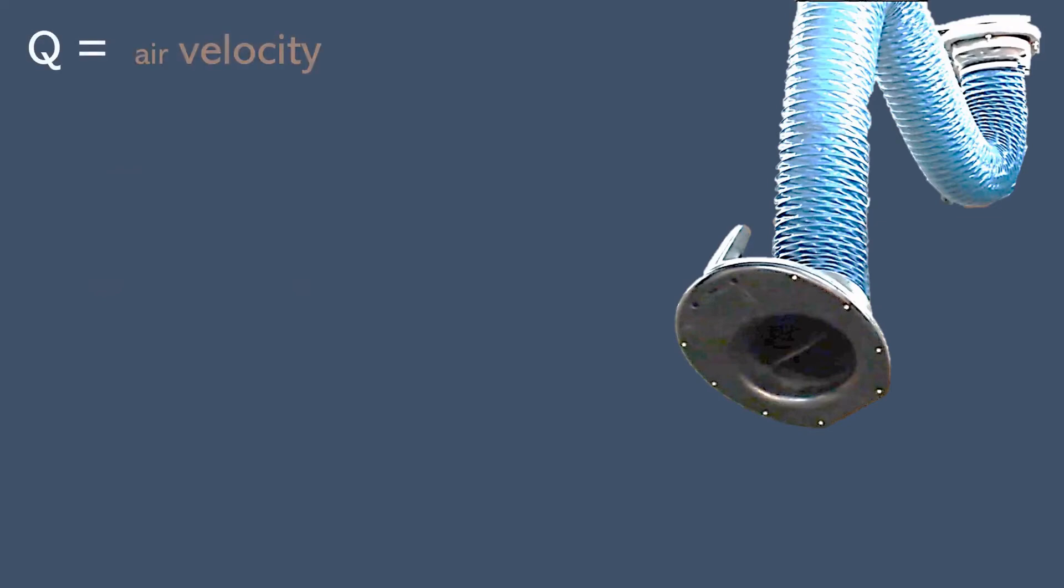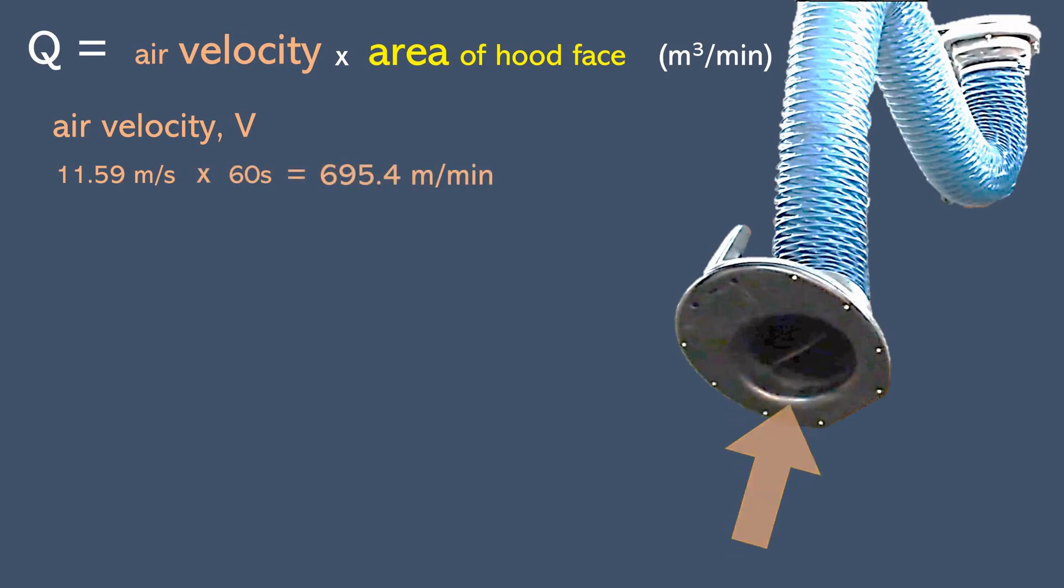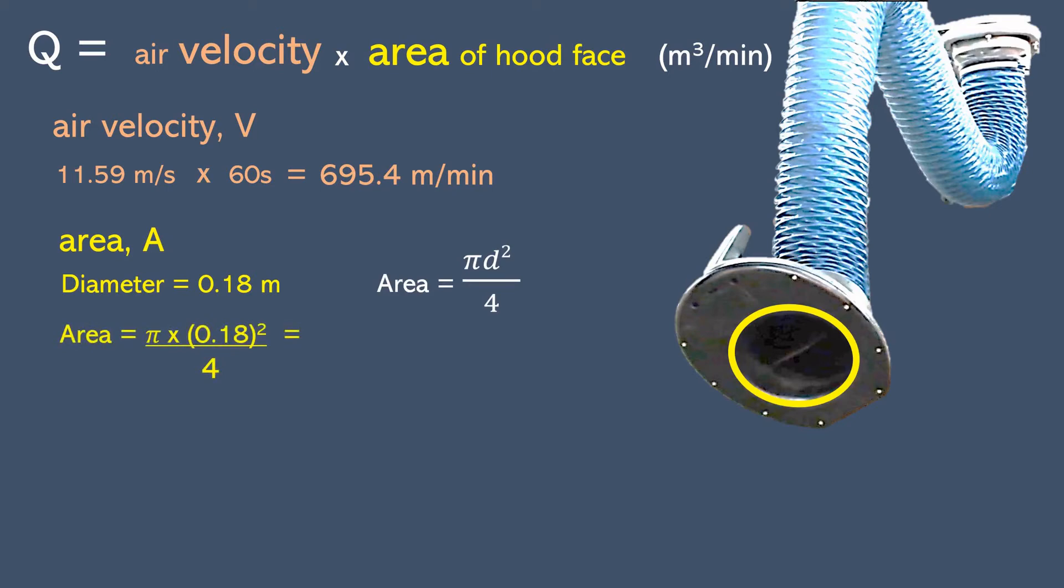Remember that we got this equation, where to get the airflow, we must have the air velocity multiplied with the hood's face area. The measurement of our air velocity by the anemometer is 11.59 meter per second. We multiply it with 60 seconds to convert it to meter per minute, and we got 695.4 meter per minute. Then for the hood's face area, when I measured the hood's face, I got diameter of 0.18 meter. Using the equation of area equal to pi d square over 4, we got the area equivalent to 0.025 meter square. So with all the values of the air velocity and the area that we had calculated, finally we got our airflow of the air that pulled into the LEV equivalent to 17.4 cubic meter per minute.